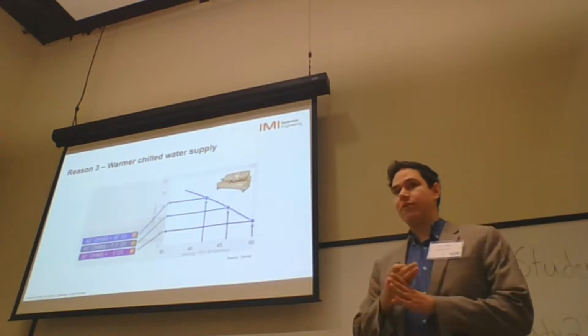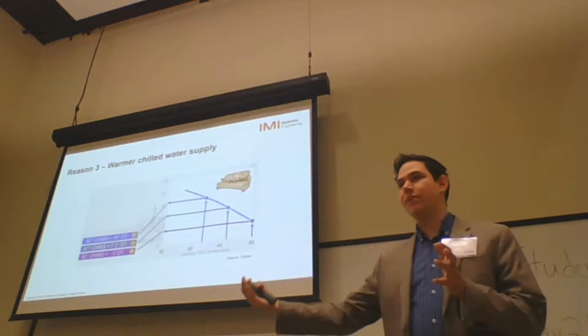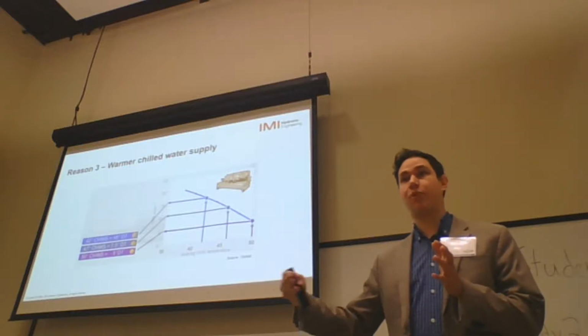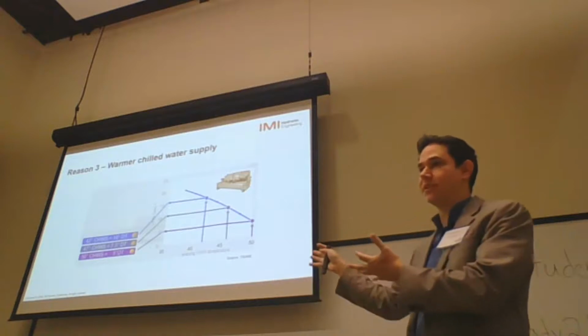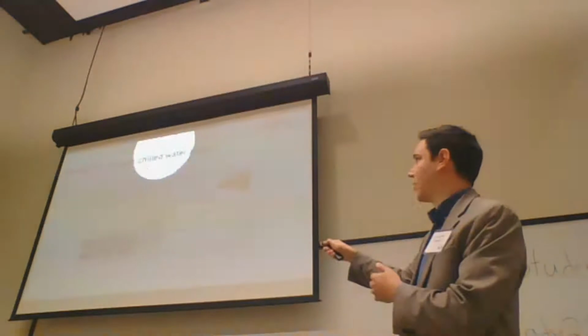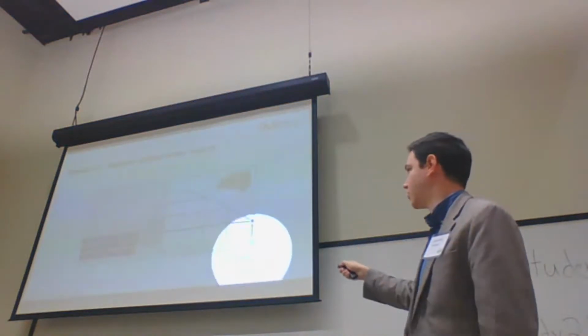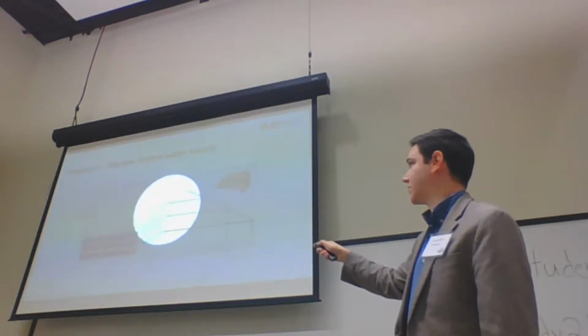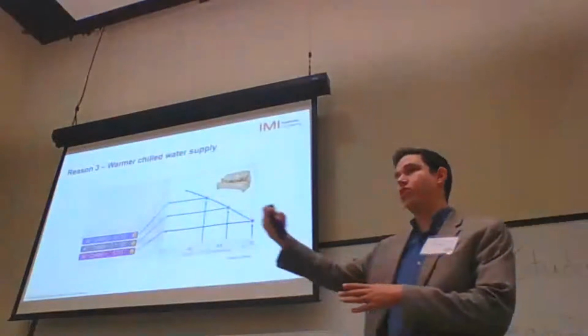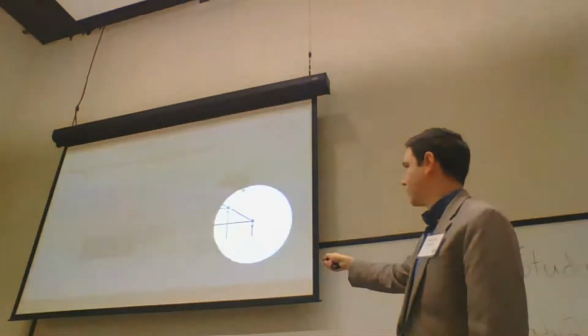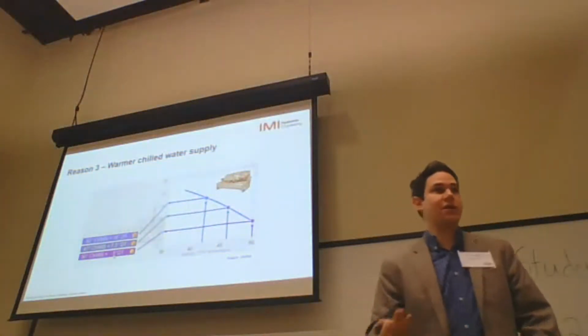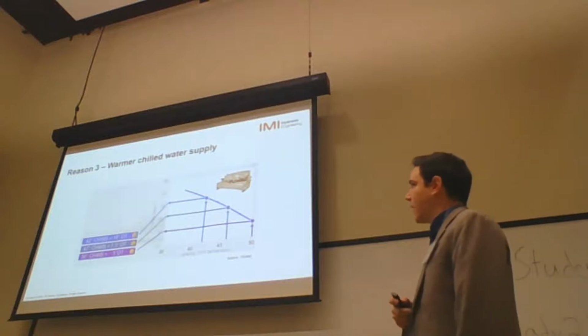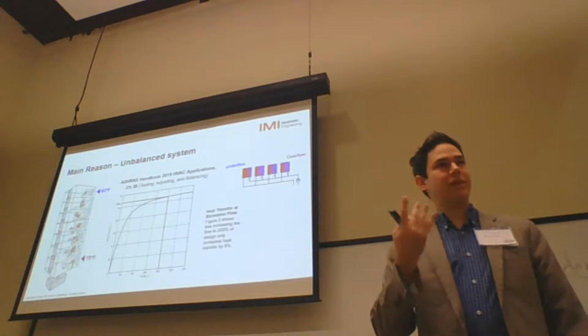Third reason, when you're thinking about the full load, I'm not talking much about ASHRAE 90.1 and resetting the chiller set point at partial load. This is more towards the full load in the system. If you're getting a warmer chilled water supply, so you're changing the supply temperature, instead of 42 degrees to get the 16 degrees delta T for your design condition, you change to 50, for example, a warmer chilled water supply for your system. You're also sacrificing the delta T performance in this case, or just wasting energy or wasting performance of the system when you do that.